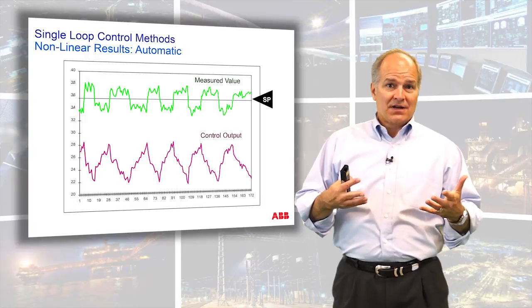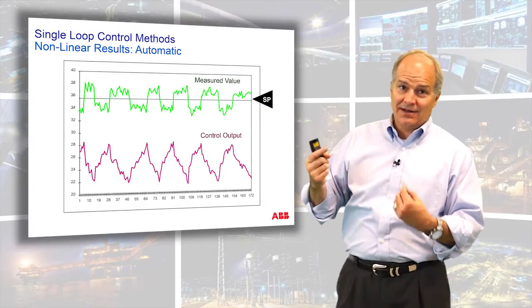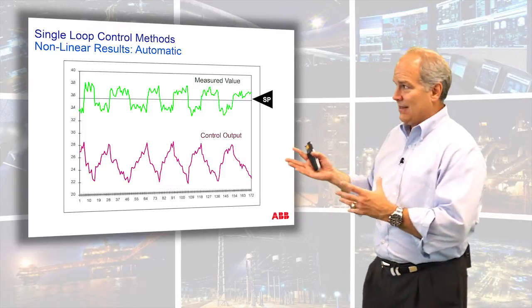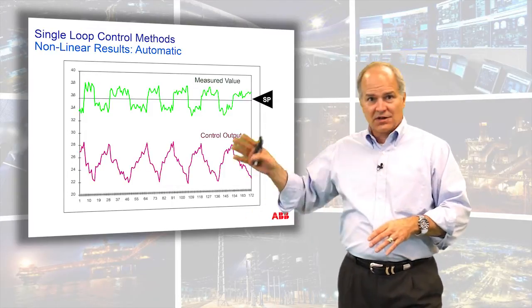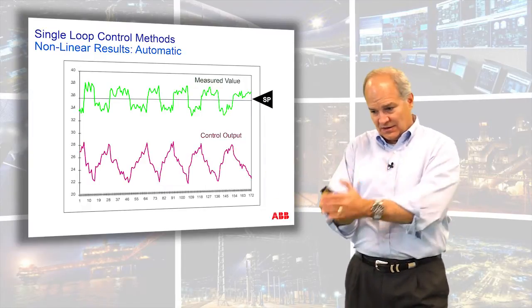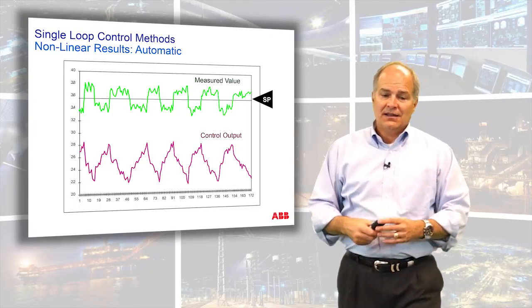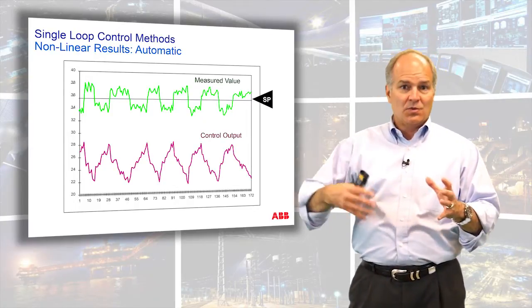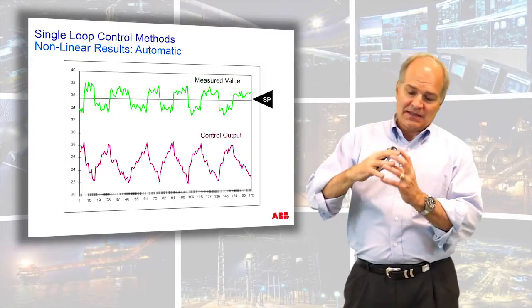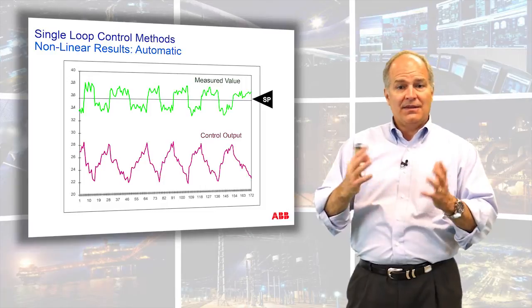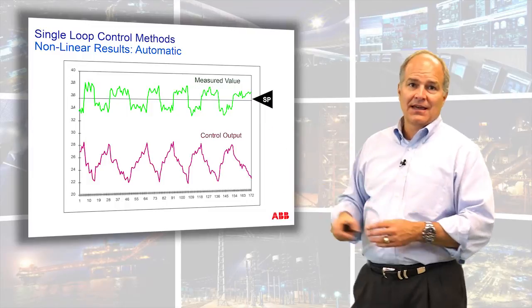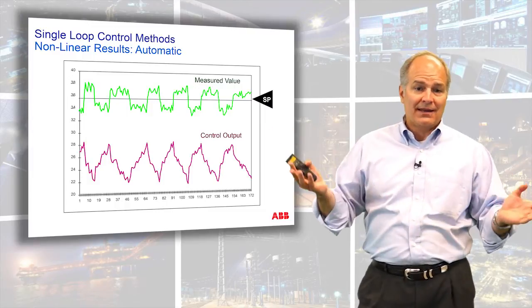If it's an integrating process, you'll get a triangle wave in the measurement and a triangle wave in the output. But it's a limit cycle. Whenever I see these, if I flip control off it'll stop; if I turn it on it starts again. I'll go and look at the actuator — if it has a valve positioner, you'll see it kind of jump back and forth. A lot of times that's just a sign that the valve positioner has worn out; they usually have a cam or fingers or gears that get stuck and break. Those are things that need to be fixed mechanically — you can't fix that with process control or by adding a dead band.